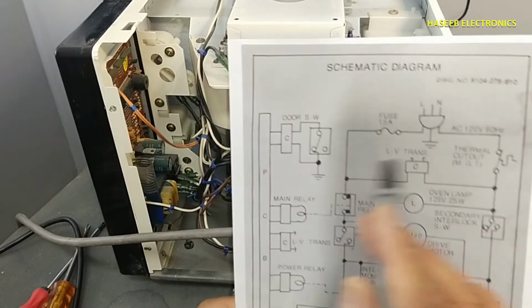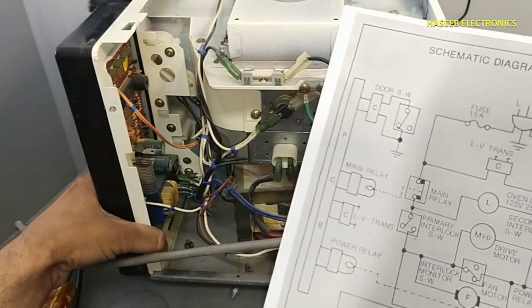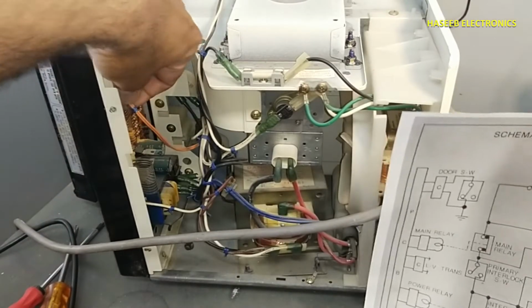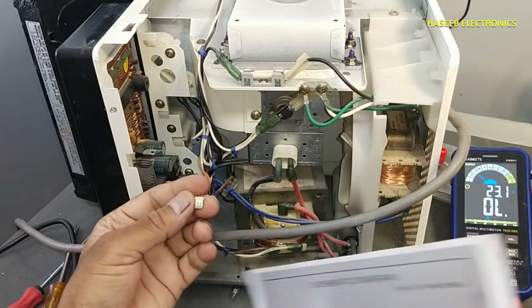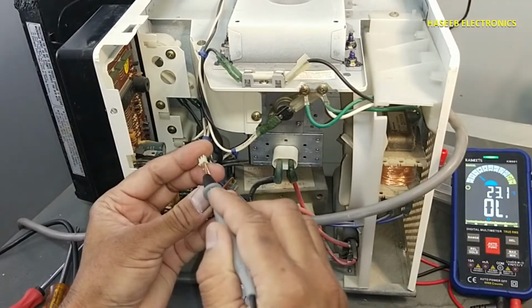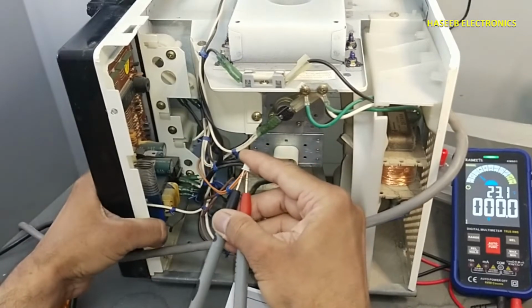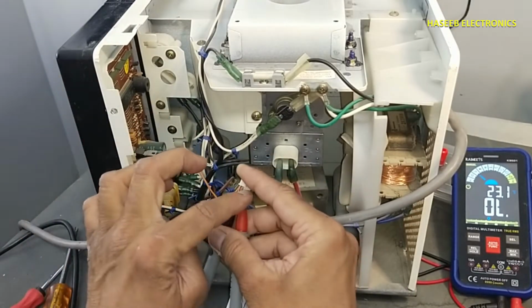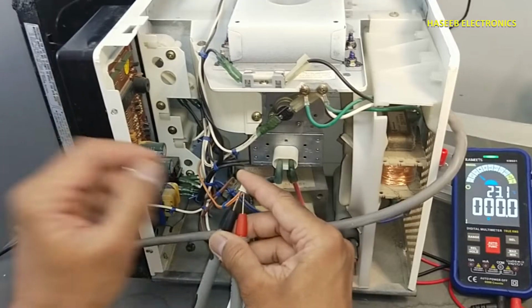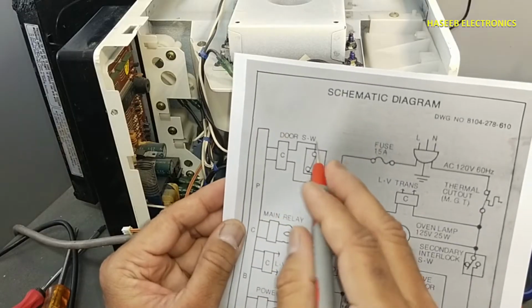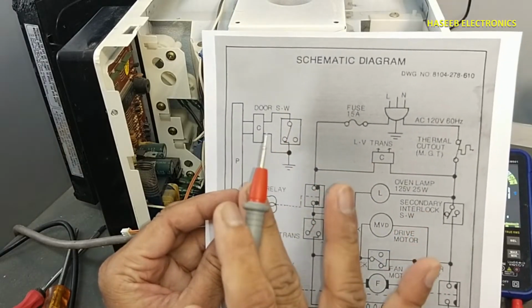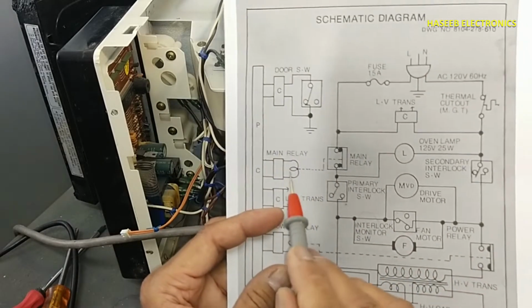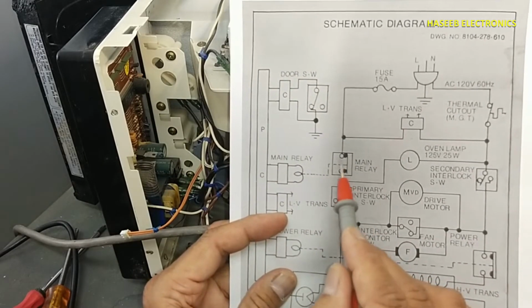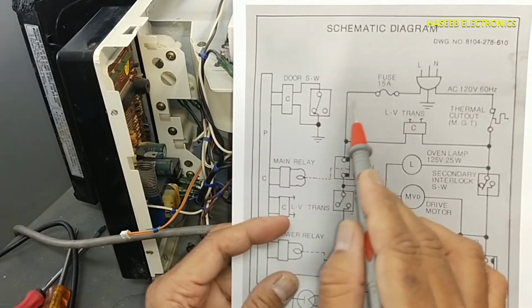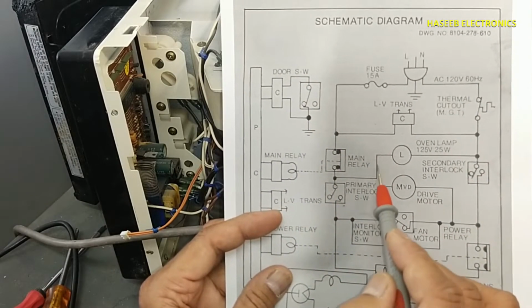When the door is opened, at that time this switch will provide continuity at these 2 points. When the door is closed, it will remain open. When it provides continuity, it gives an interlock signal that the door is opened. When the door is opened, at that time it will turn on this relay. When this relay turns on, this voltage will reach here and go to the lamp.